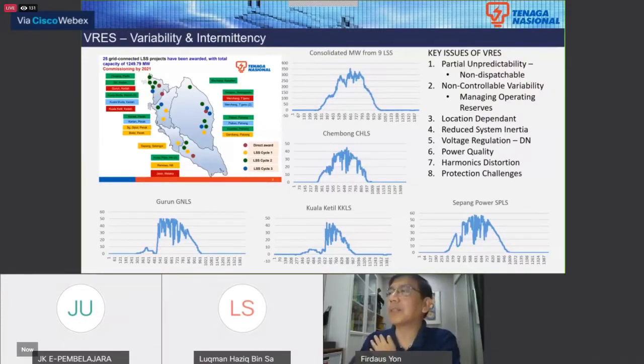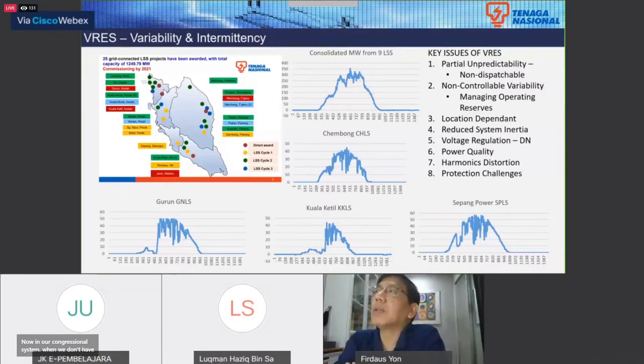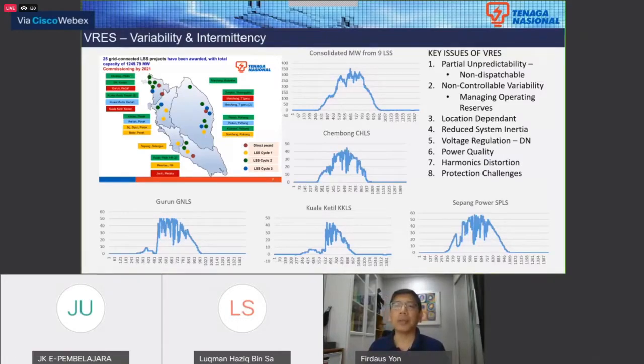In our conventional system, when we don't have solar, the rule is that we have spinning reserve - machines that are synchronized to the system, meaning they're rotating, but not producing load or not producing their full load. So when a generator trips, or in this case solar stops producing, this spinning reserve will take up the slack and pick up the load. Because it's already on the bus and already spinning, it will automatically ramp up to pick up the load. That is spinning reserve.